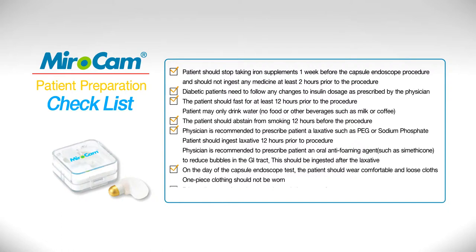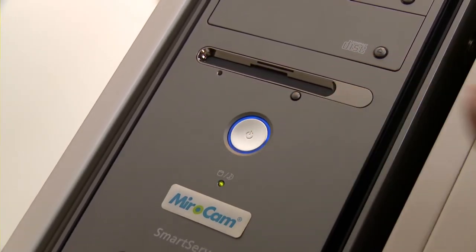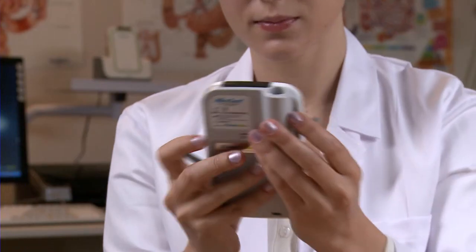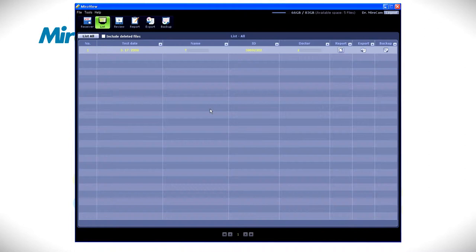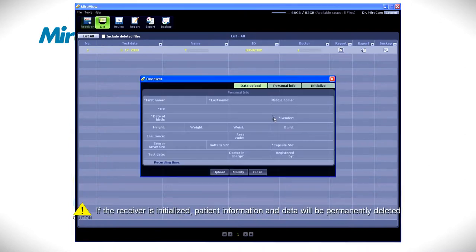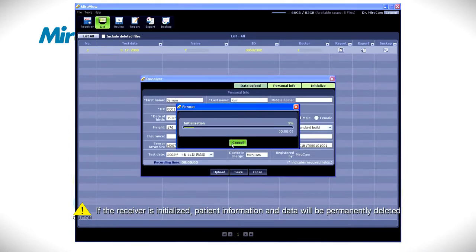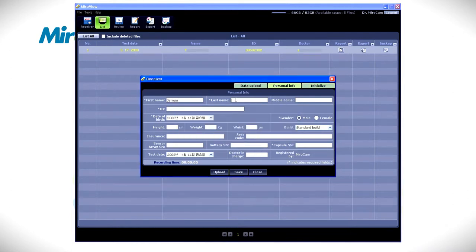Patient Administration: Confirm patient has followed the preparation accordingly and begin the administration procedure. Nurse or medical practitioner should turn on the computer, start MiroView, and log in. Connect the receiver to the computer via the USB cable and make sure the receiver is turned on. After clicking the receiver button, click Initialize. After initialization, enter the patient data.